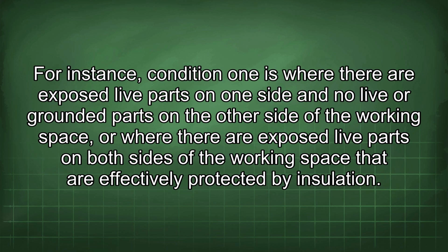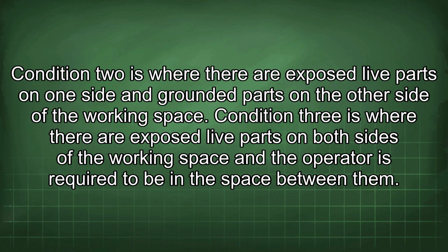For instance, condition 1 is where there are exposed live parts on one side and no live or grounded parts on the other side of the working space, or where there are exposed live parts on both sides of the working space that are effectively protected by insulation. Condition 2 is where there are exposed live parts on one side and grounded parts on the other side of the working space. Condition 3 is where there are exposed live parts on both sides of the working space and the operator is required to be in the space between them.